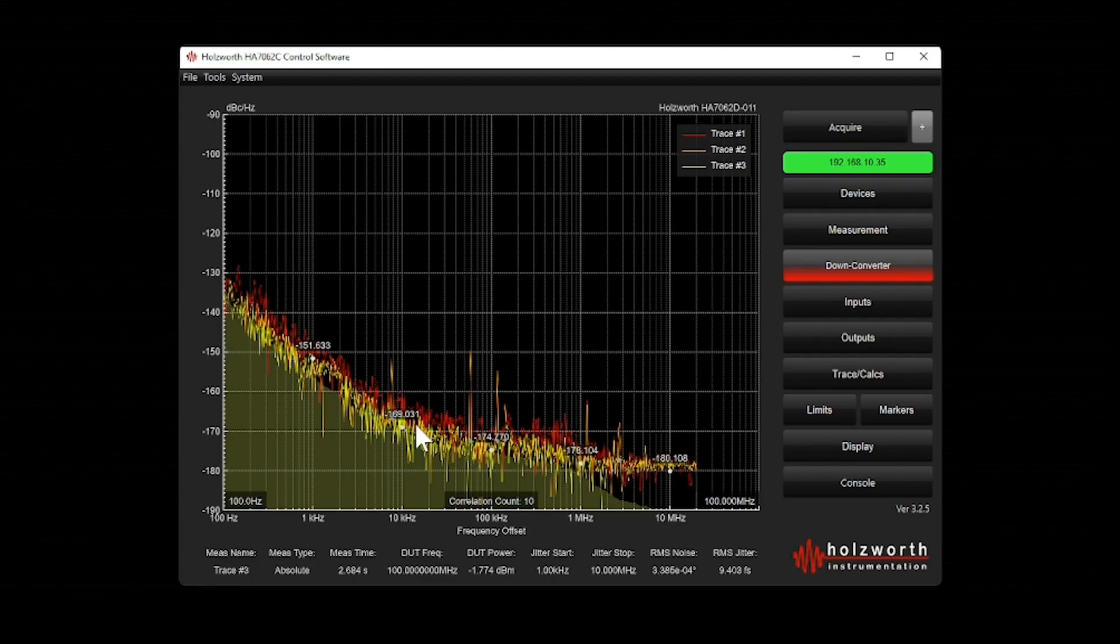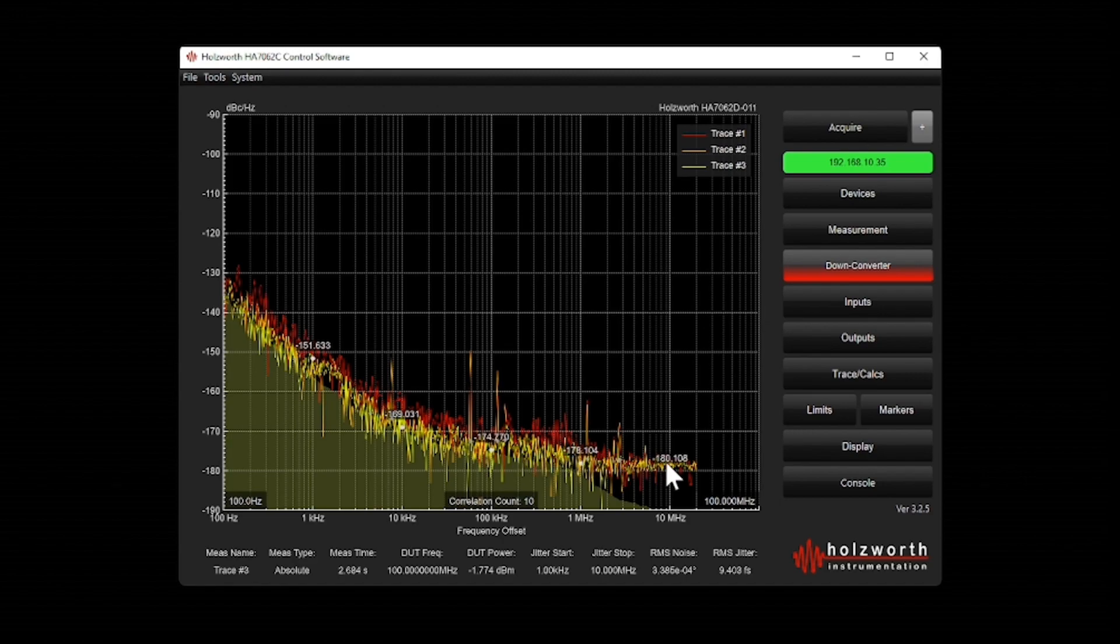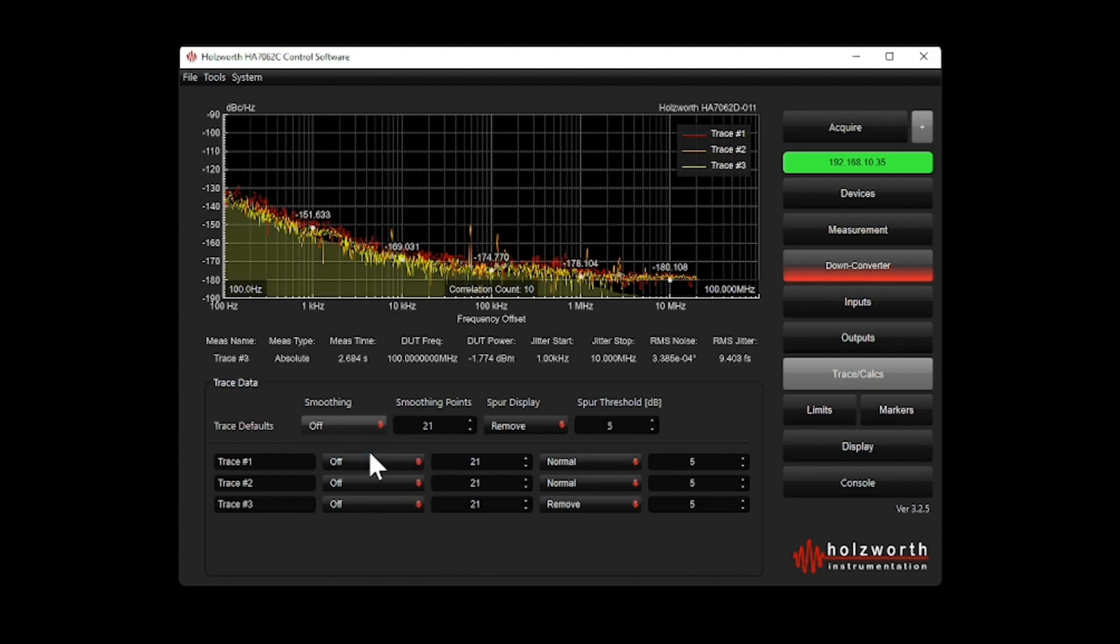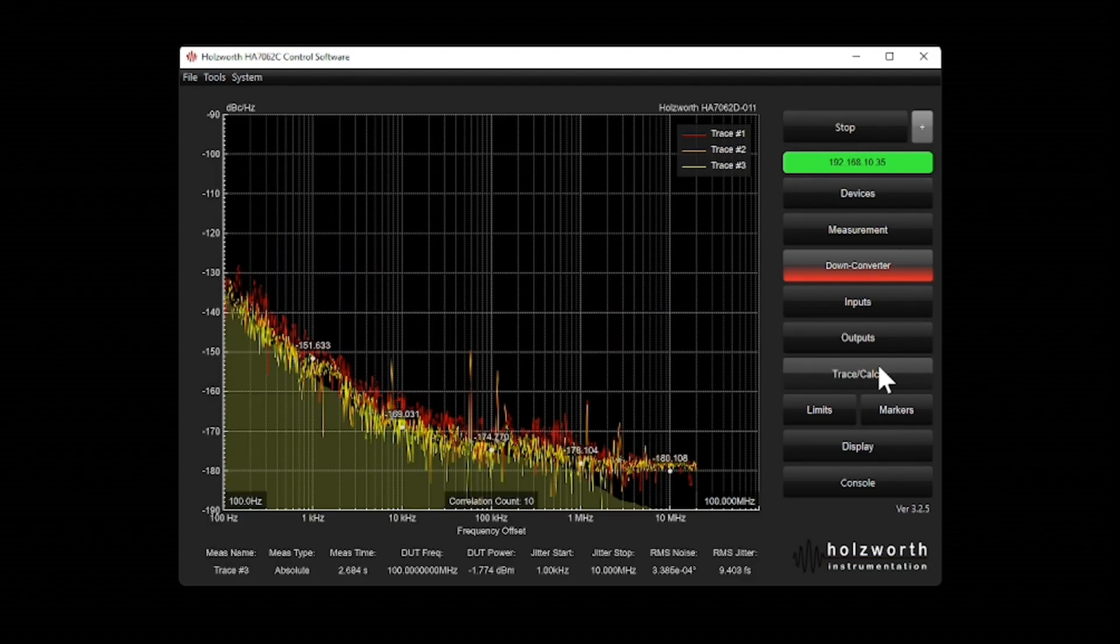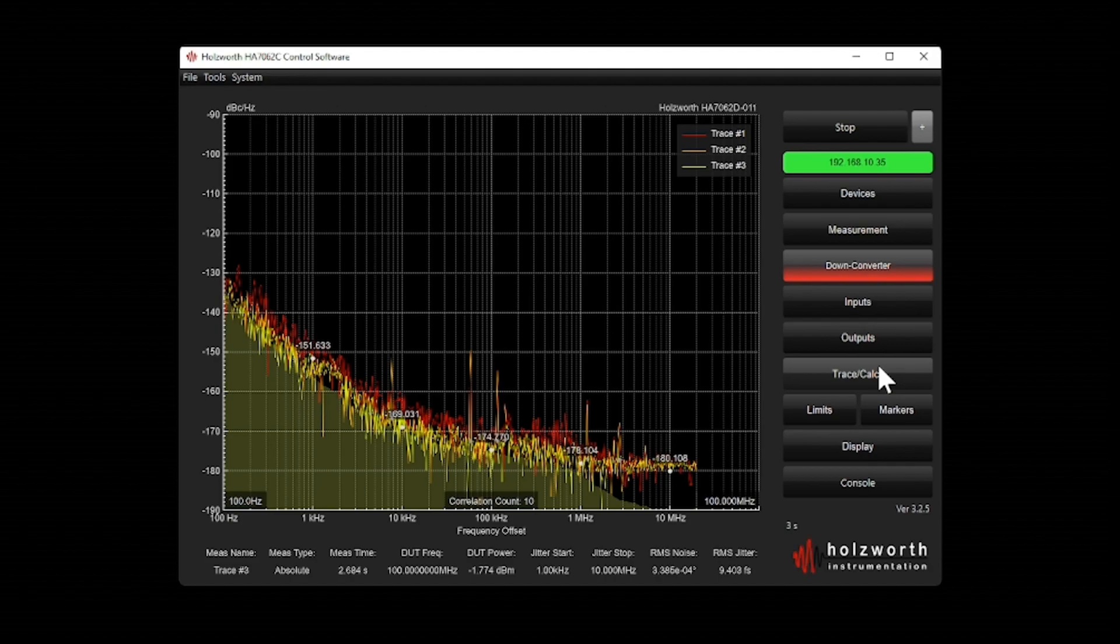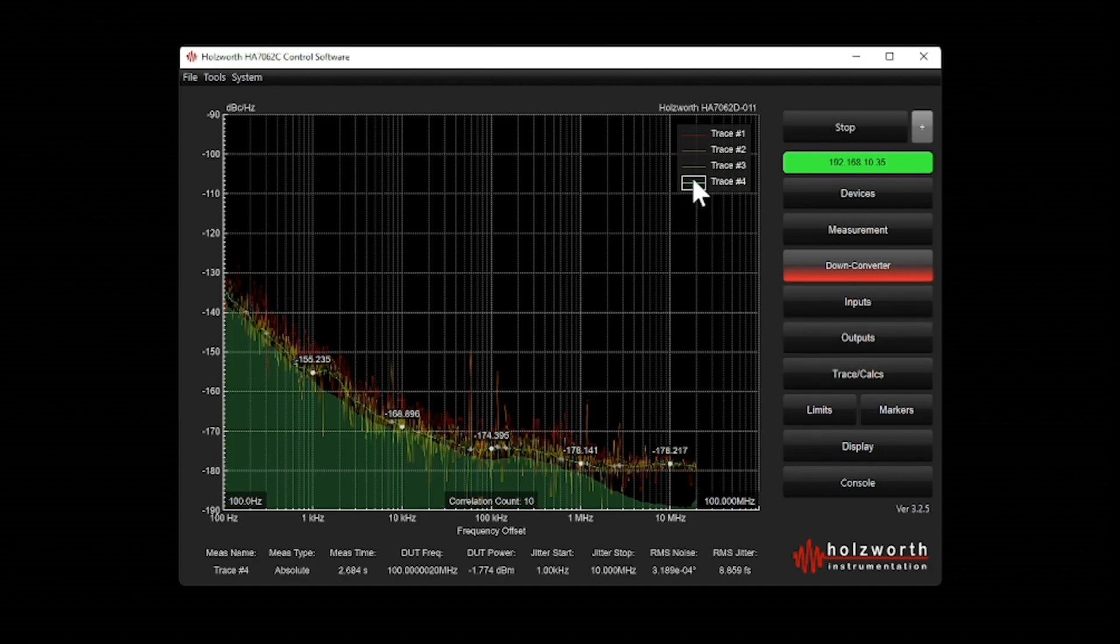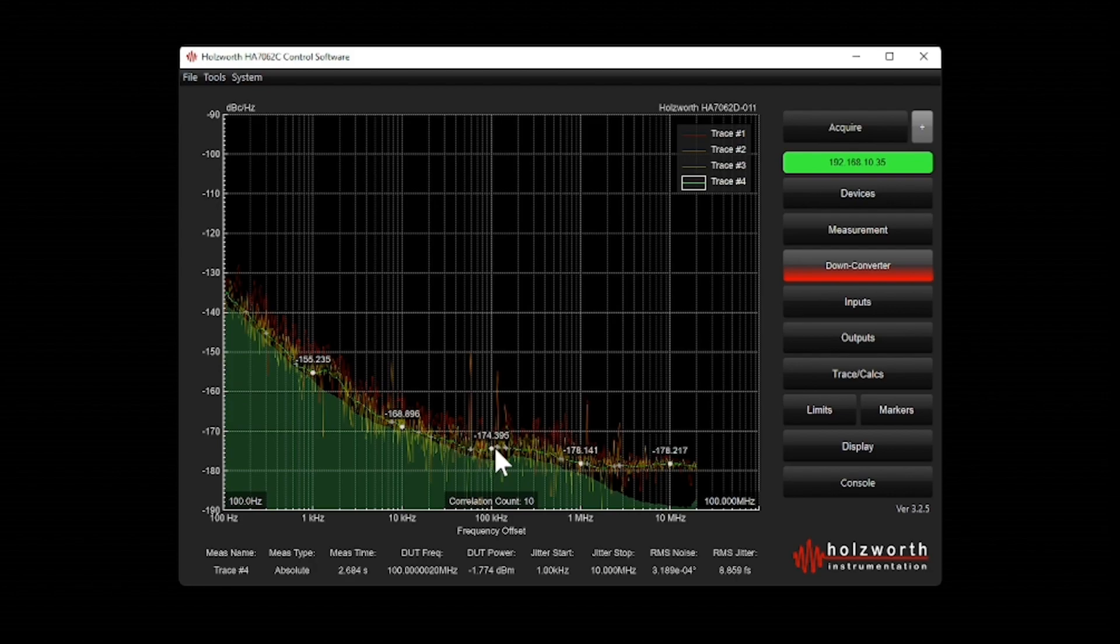The signal is still fairly noisy. If I want to get a clearer picture of the phase noise, I can add smoothing. Going back into my trace tab, I can turn smoothing on. Let's acquire again. Now, if I focus on that particular trace, you can see I have a nice, smooth plot of the phase noise of this oscillator.